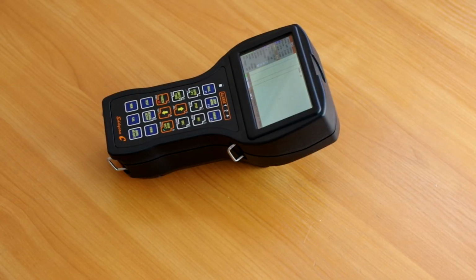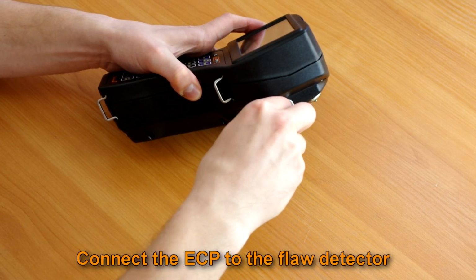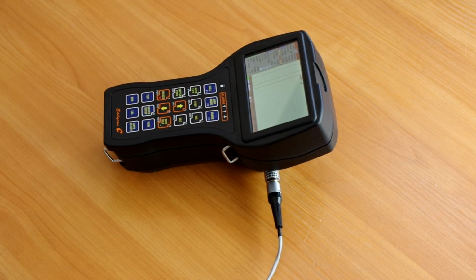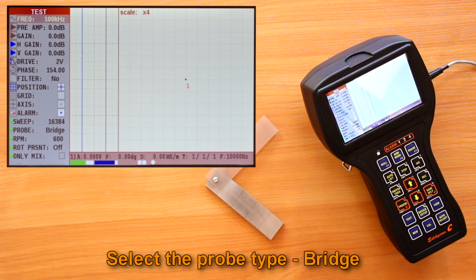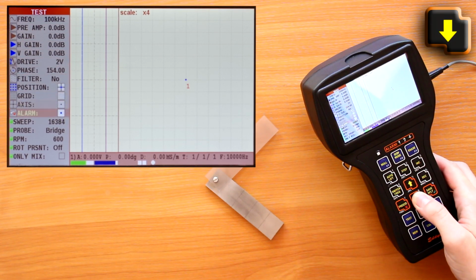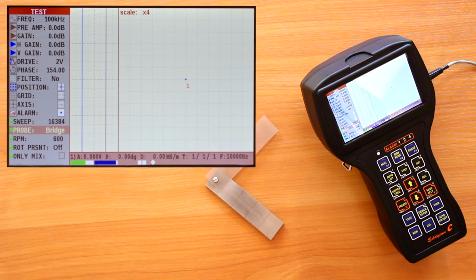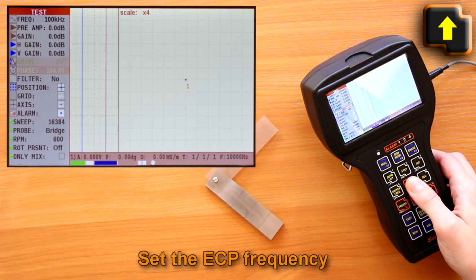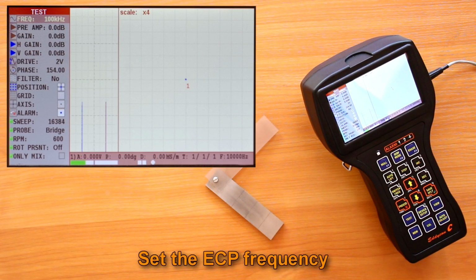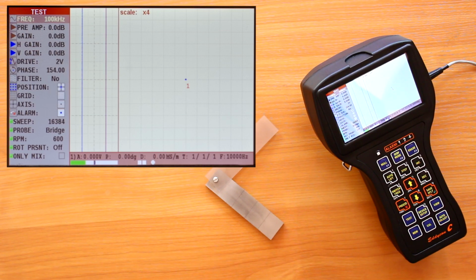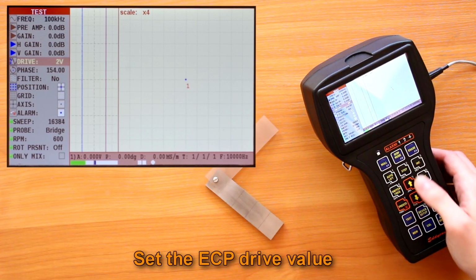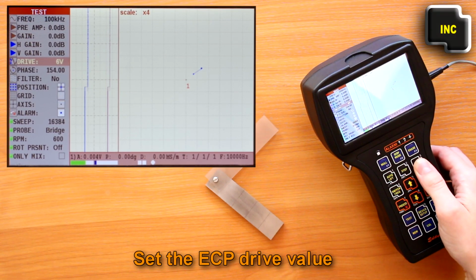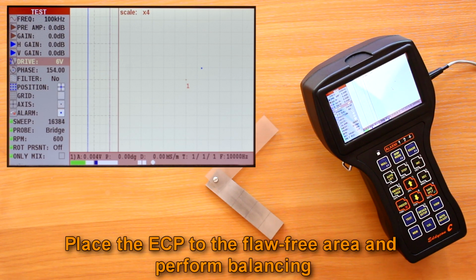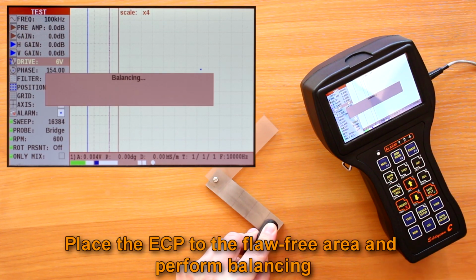Bridge probe. Connect the ECP to the flaw detector using a connecting cable. Select parameter probe in the test menu, bridge type. Set the ECP frequency in a range specified in the registration certificate of the ECP or on the probe marking. Set the ECP drive not more than recommended in its registration certificate. Place the ECP to the flaw-free area of a calibration block. Press the F1 key to balance the ECP.